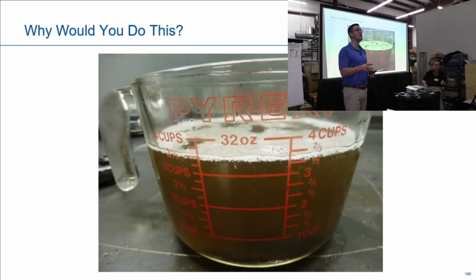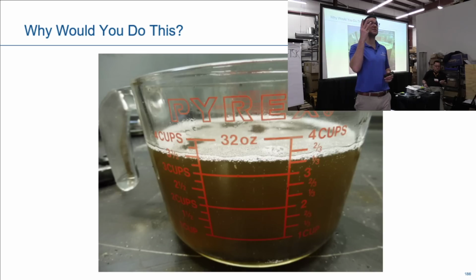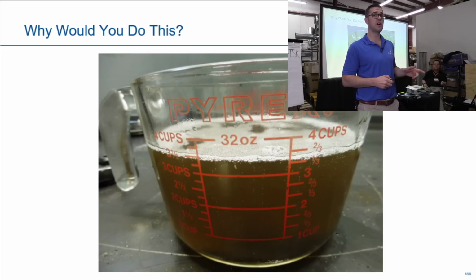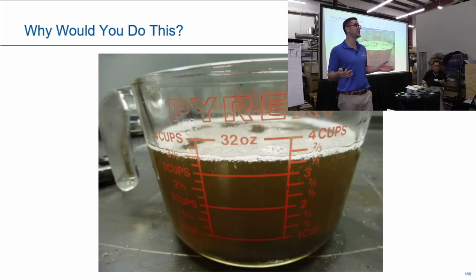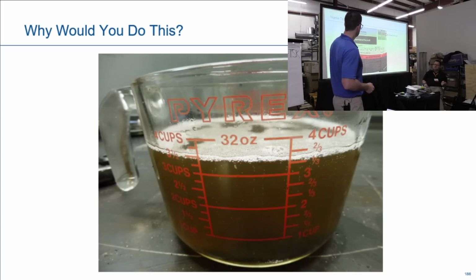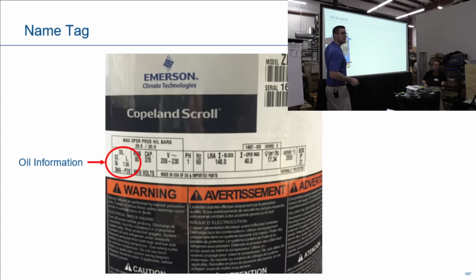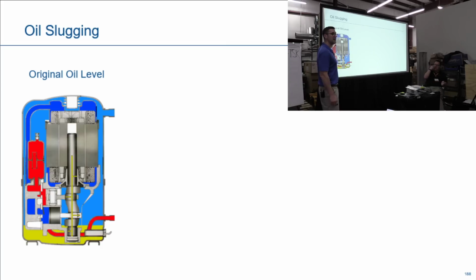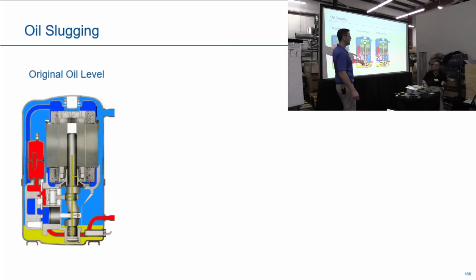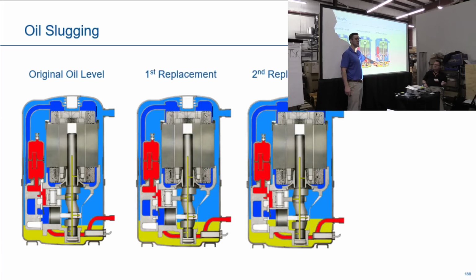Okay? So now that compressor was replaced 3 times. It was a new contractor that took over because he was like, why did this fail? I just replaced it. He's a new contractor on site. Didn't know the site before because the owners hired another contractor to see what's going on because there were multiple failures. So what happened? The first contractor, original one failed. Then another one failed. Watch the oil. Then a third one failed. Or second replacement, sorry. And then this is when the other contractor came in and this one failed.